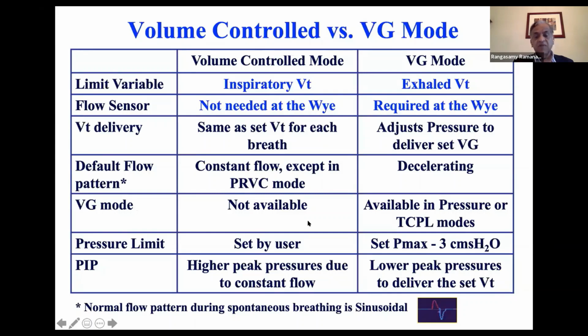Volume guarantee mode is not available here; it is available in pressure control or TCPL mode, time cycled pressure limited, plus VG, assist control plus VG. The pressure limit is set by the user. Here you don't have to set the PIP. You just set the Pmax at 30, and then once the ventilator reaches 27, it'll give you an alarm. If it's at 35, it'll alarm when the ventilator has to use 32 centimeters. In volume control, usually higher peak pressures are required, as the flow is constant, whereas here you can deliver the same tidal volume using lower PIP. So that's the advantage of volume guarantee mode.